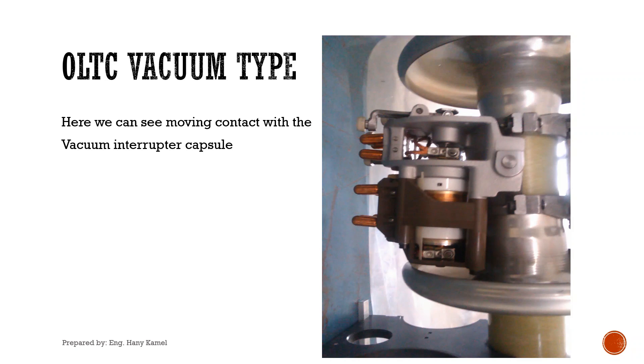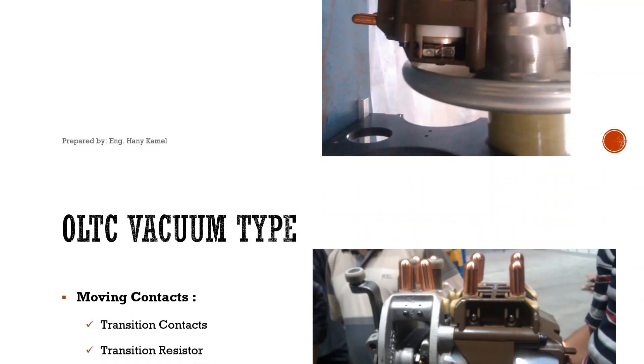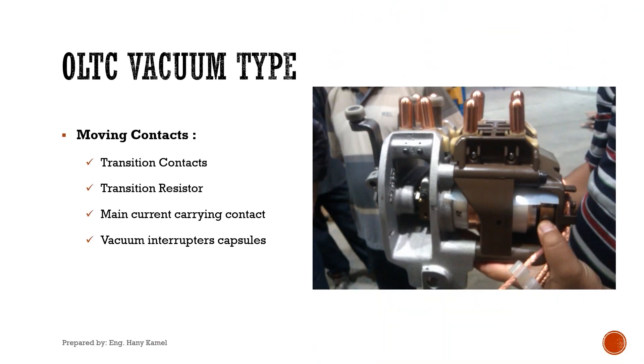Moving contacts of the vacuum type include: transition contacts — unlike the oil tap changer type which has two transition contacts, the vacuum type has one; transition resistor, same as before; main current carrying contacts, same as before; and vacuum interrupter capsules, which interrupt the arc during tap changing.